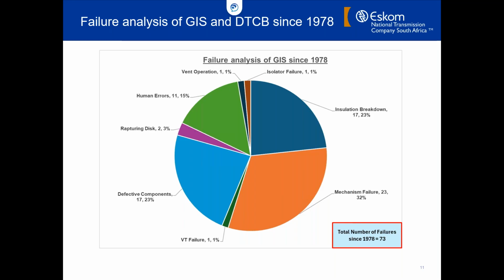Defective components and insulation breakdown are heading head to head with 23%, or in total 17 in each of those categories. And insulation breakdown is unfortunately one of the most risky parts of SF6, due to the fact that we're running under high pressure, and also that we are in very close proximity between your live and your earth conductors or your enclosures. So insulation breakdown is a very important point. That's why it is so important to ensure that the quality of the SF6 is monitored on a regular basis, checked and verified, and that it is within the specs. And that is one of the maintenance aspects as well.